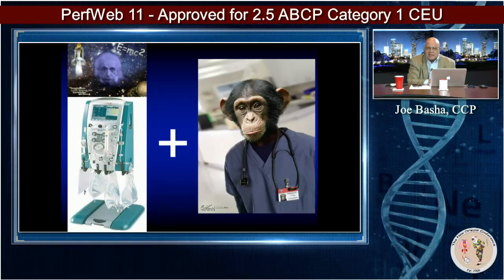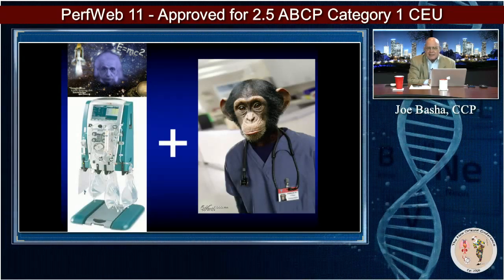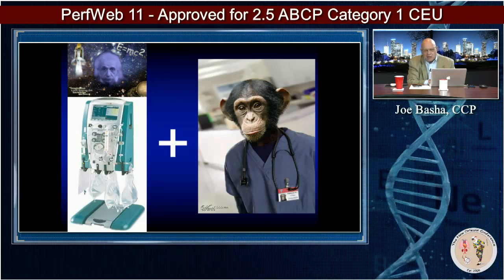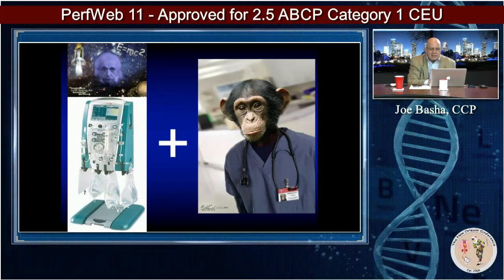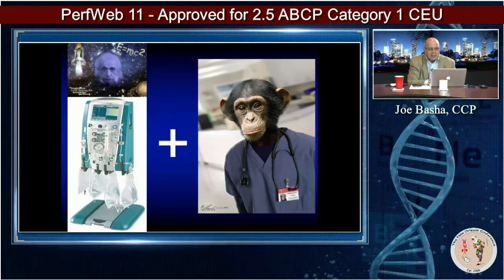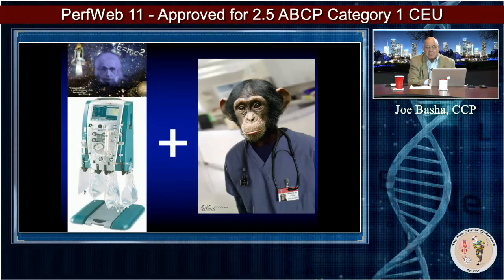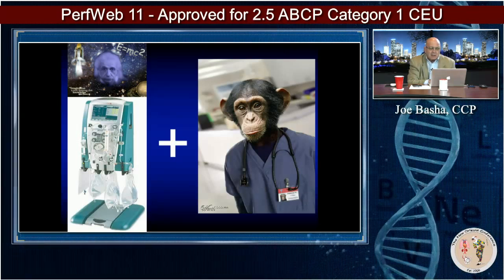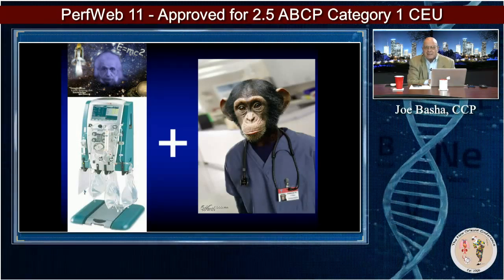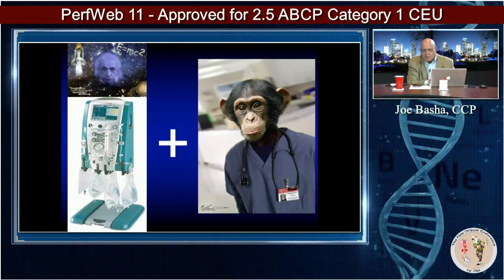So I see that as an advantage, but again, if you bump it, that makes it alarm and shut off and you have to reset it. If the scales go bad, it's going to be a problem, of course. You need to recalibrate them. You're changing bags.